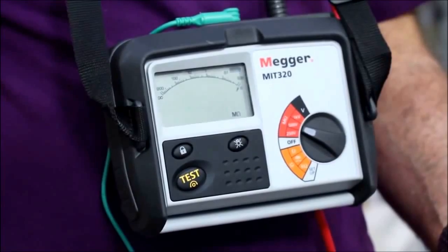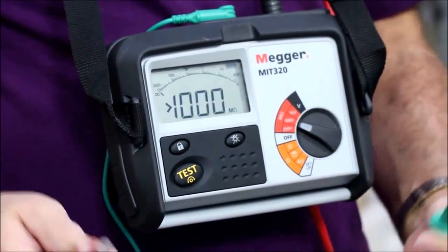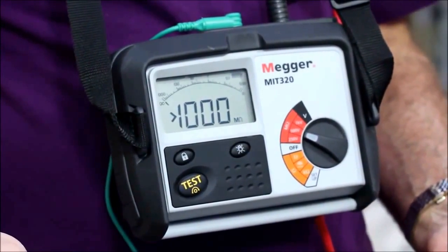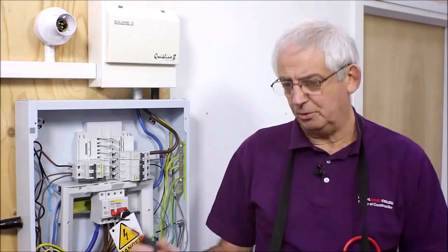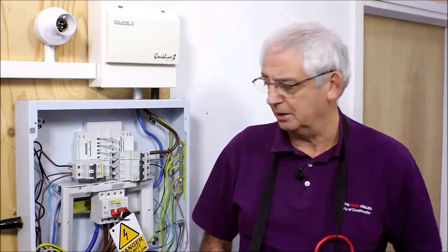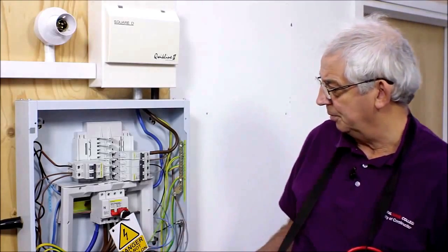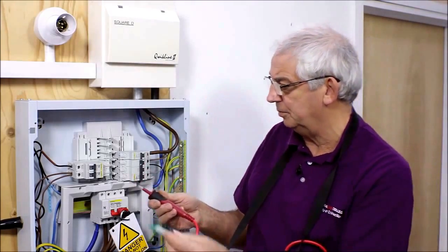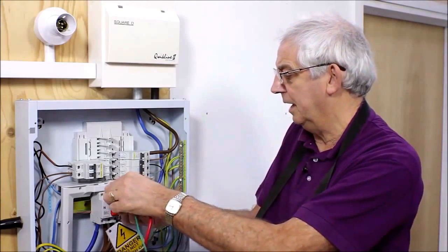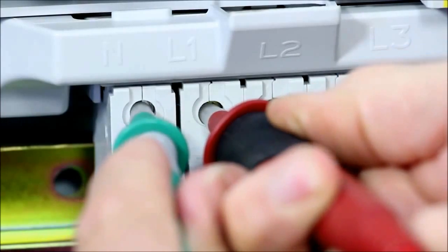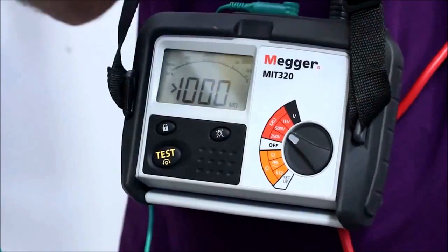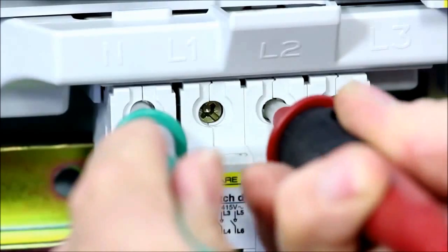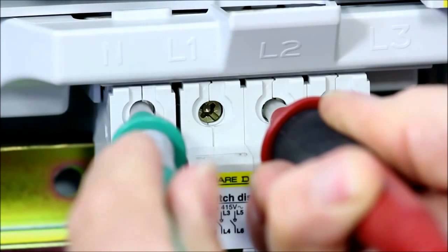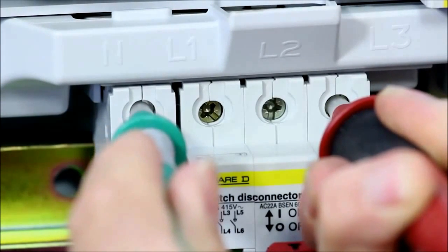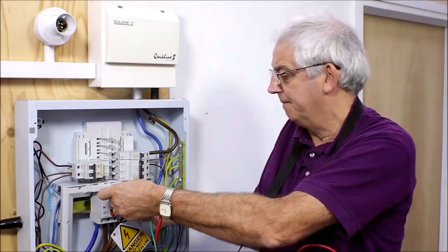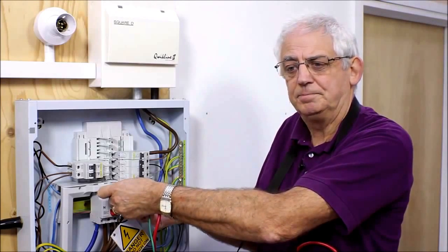Carry out the same test with the leads apart, push the button again, and now the reading should be over range. Okay, with that done, I know full well that the instrument is working properly. So all I need to do now is go to the board and test between, first of all, line and neutral, push the button, and again I've got a reading that's over range. L2 to neutral, again reading over range. L3 to neutral, again reading over range.